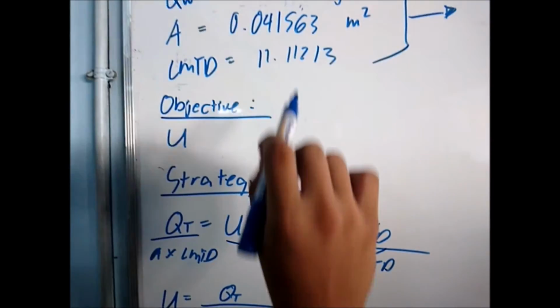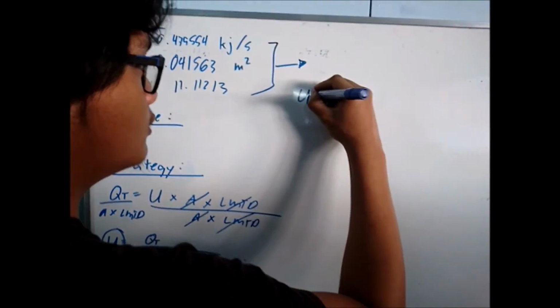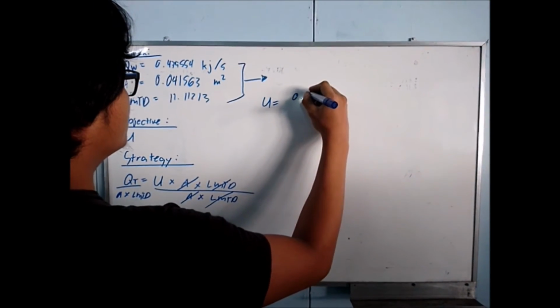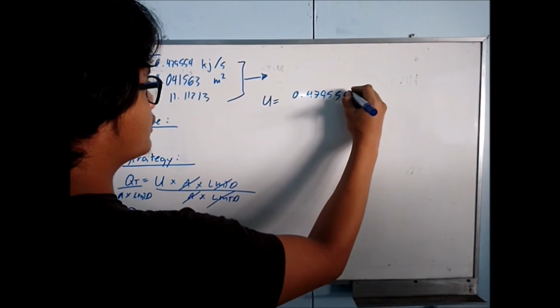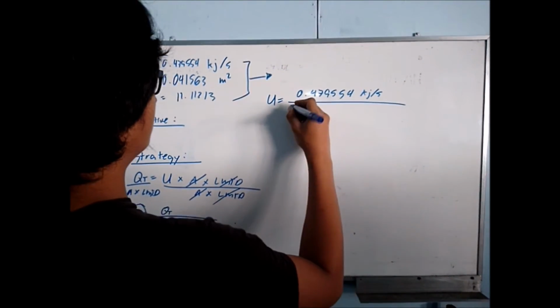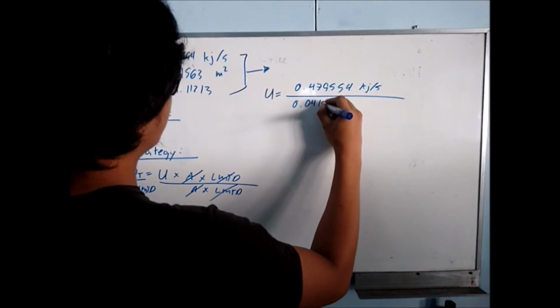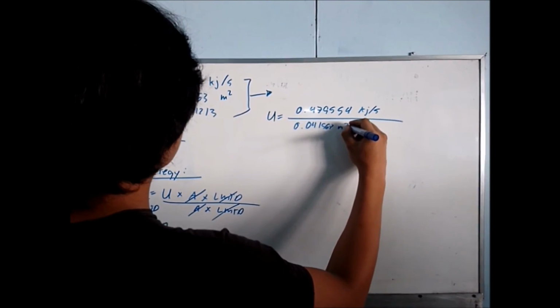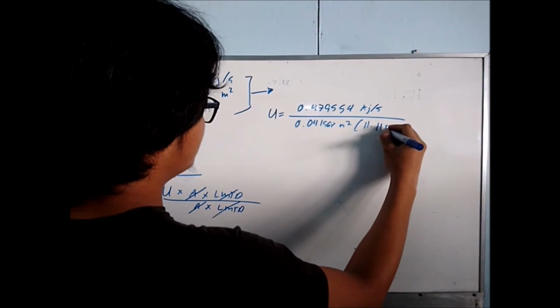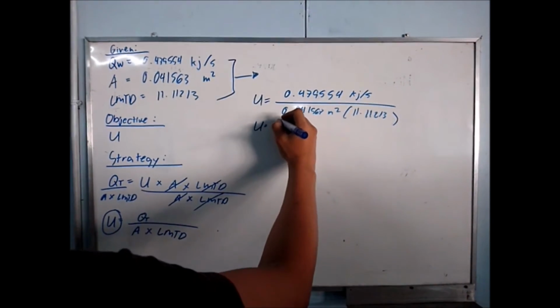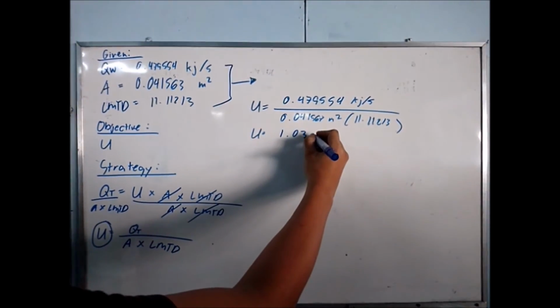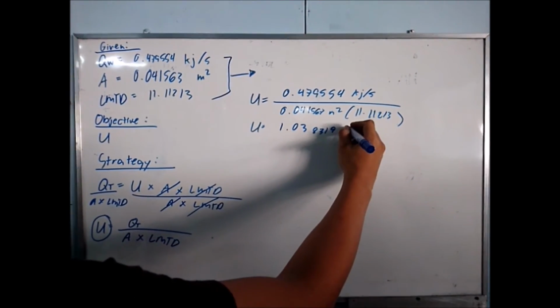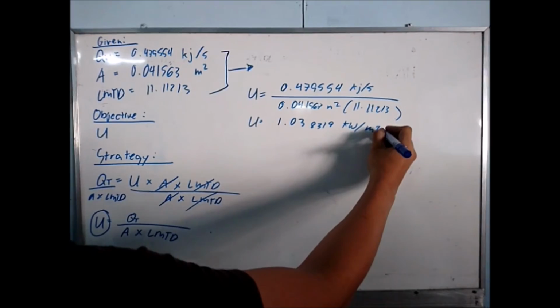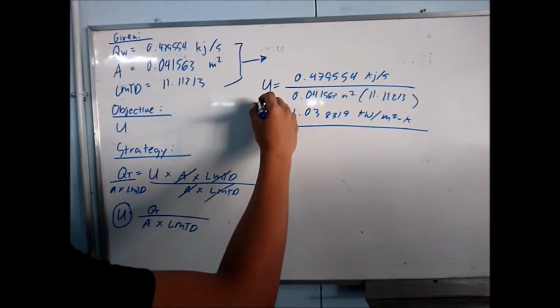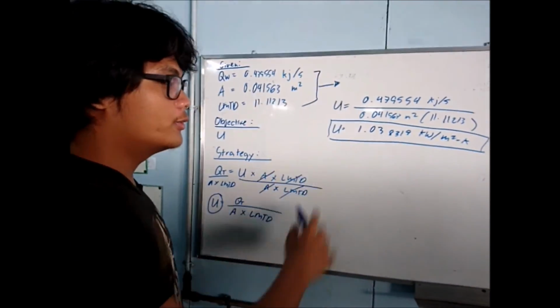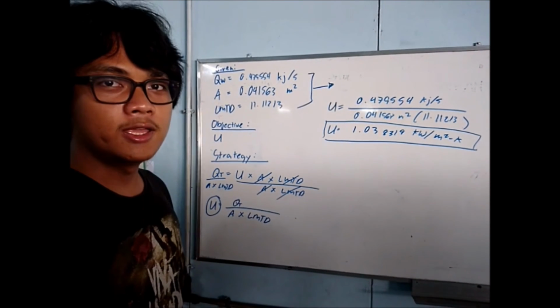Now, we will use these values to compute U. U is equal to 0.47955 kilojoules per second over 0.041563 meter squared multiplied by 11.11213. And we yield the value 1.038319 kilowatts per meter squared Kelvin. This is the overall heat transfer coefficient of the heat exchanger system.